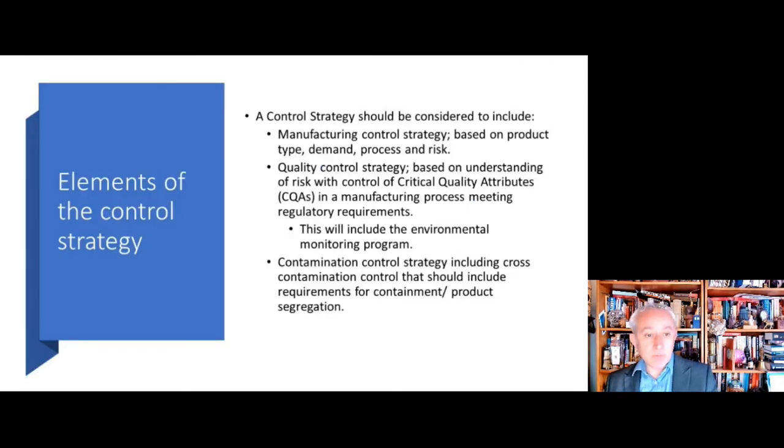In terms of some of the other elements, and I keep going back to this theme of everything being connected together, you need to also feed in the contamination control strategy to a manufacturing control strategy, so there may be nuances based on product type, demand, process, and risk. A quality control strategy, so we have some understanding of critical quality attributes. Environmental monitoring should be connecting with that. And also cross-contamination if we're using very different products with different active ingredients in the same facility, then the containment product segregation aspects will also be of importance.